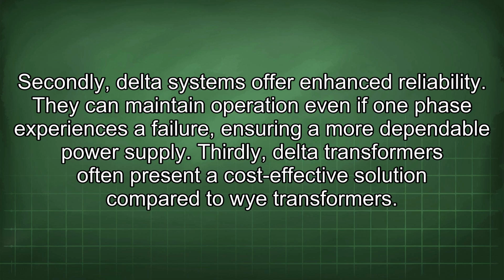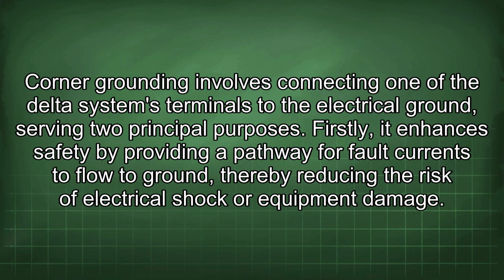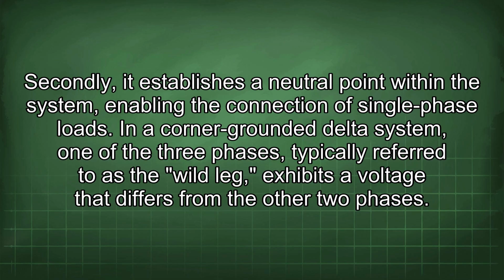Thirdly, delta transformers often present a cost-effective solution compared to Y transformers. Corner grounding involves connecting one of the delta system's terminals to the electrical ground, serving two principal purposes. Firstly, it enhances safety by providing a pathway for fault currents to flow to ground, thereby reducing the risk of electrical shock or equipment damage. Secondly, it establishes a neutral point within the system, enabling the connection of single-phase loads.